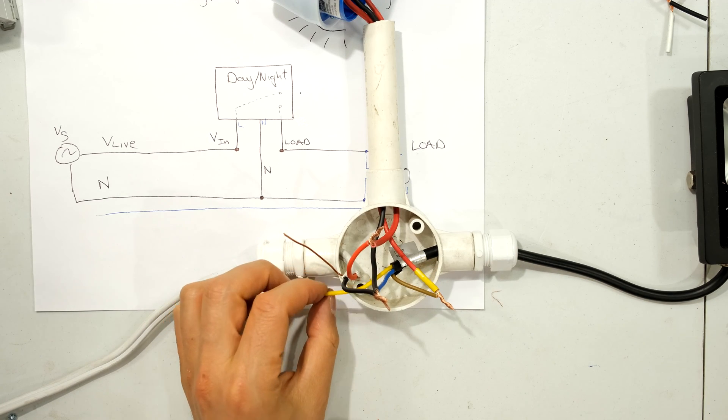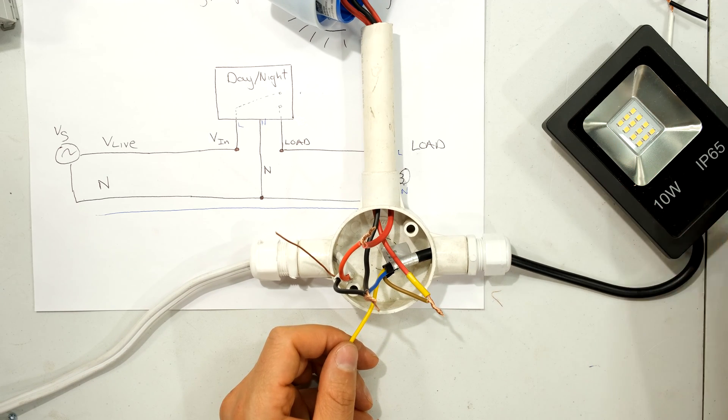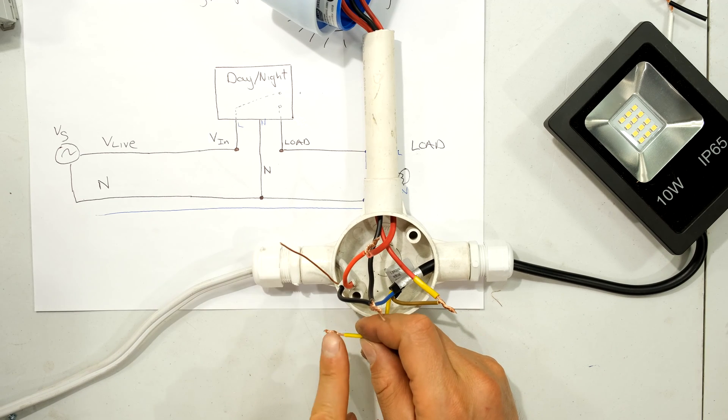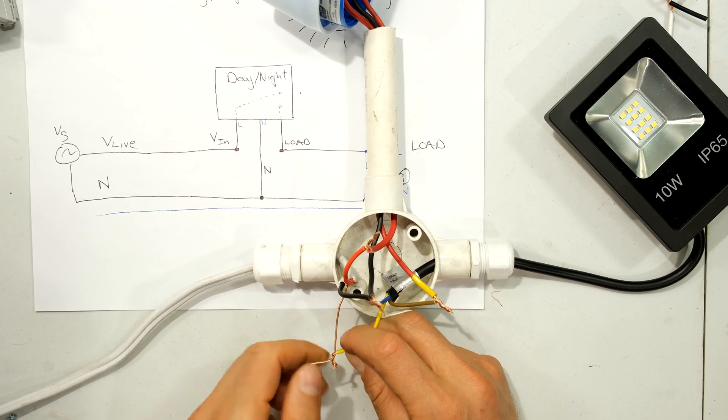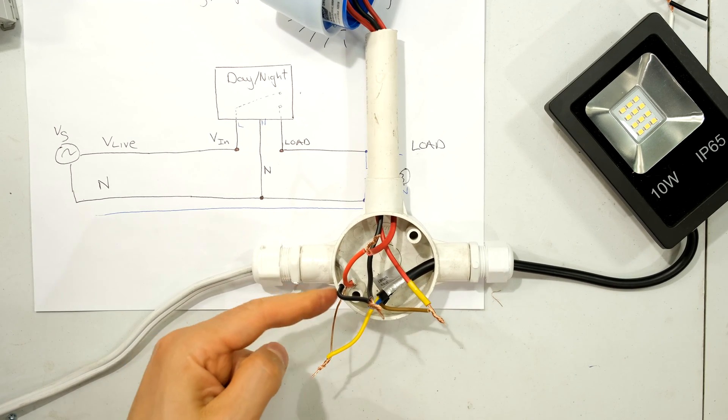Now you may notice there's an earth wire sitting here. And the reason why there's this earth wire is because the day-night switch has this chassis or this metallic surface. So I need to connect the earth to the earth of my supply. So there we go. I now have my earth connecting to the earth that came from my supply.